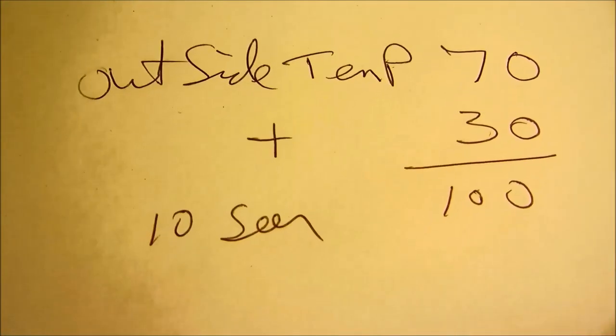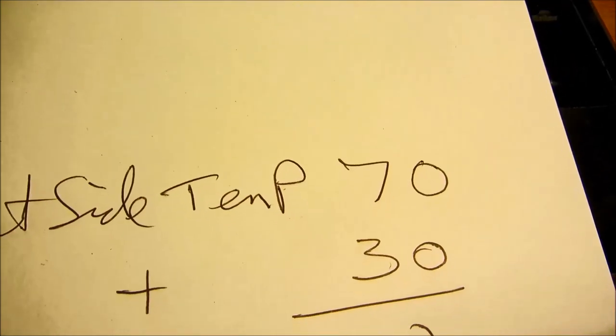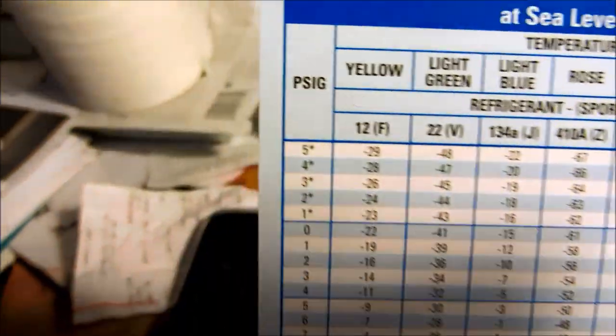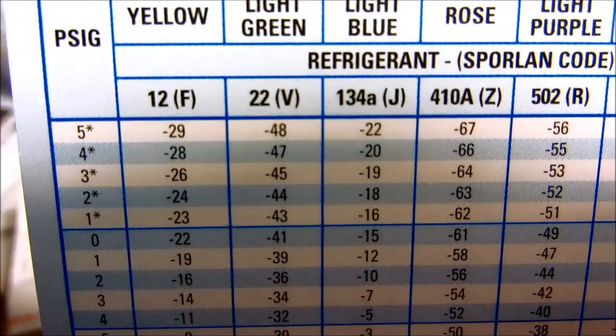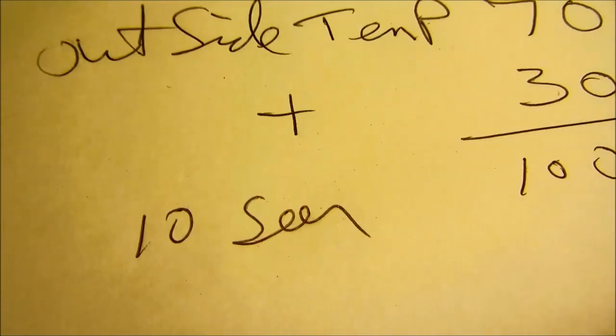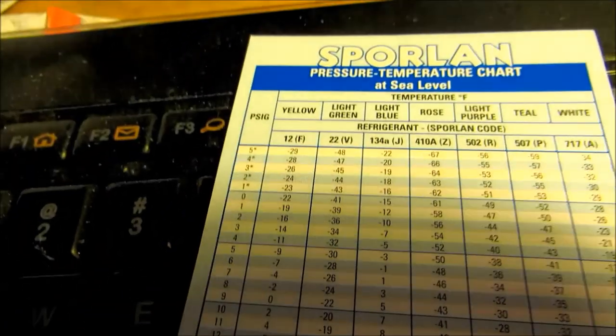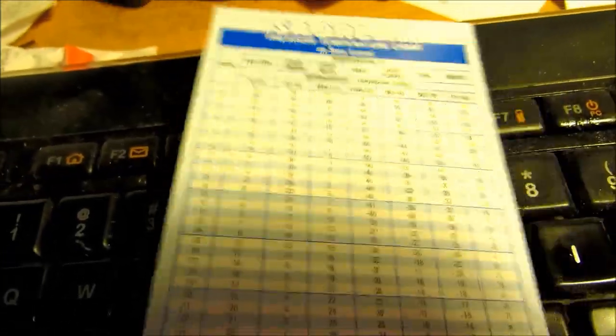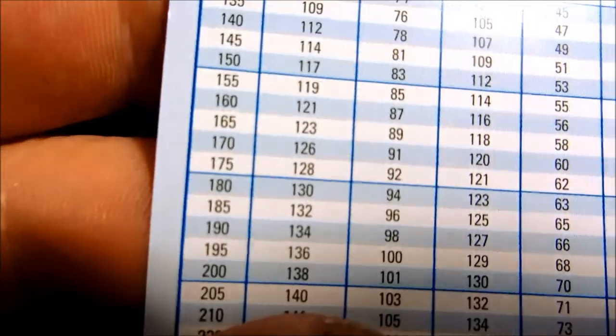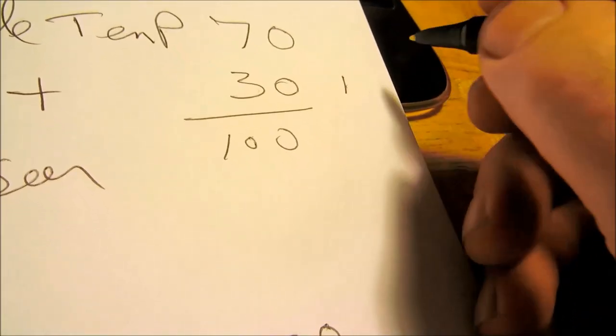The 30 rule for 10 SEER units: outside temperature plus 30 would give you 100. You come over to your PT chart. The second column is R-22. If your outside temperature is 70 and you got a 10 SEER unit, you add 30 to 70 so you got 100. Go down the R-22 scale to 100.